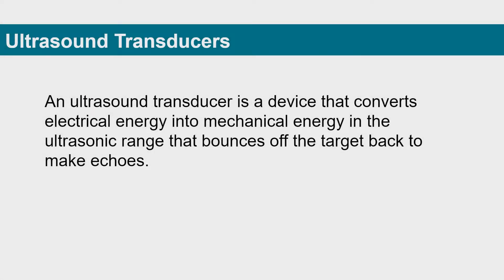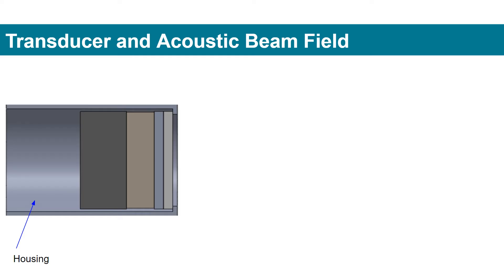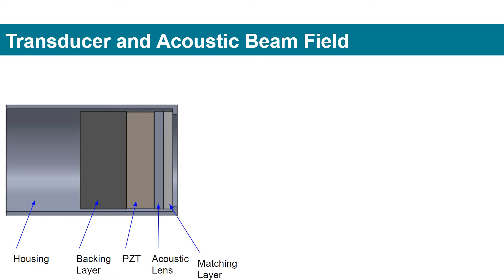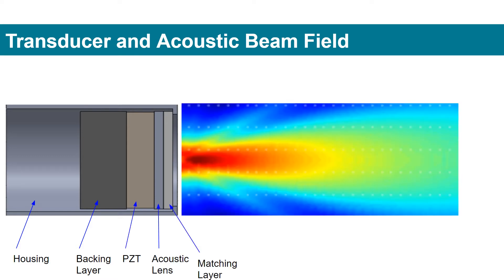An ultrasound transducer is a device that converts electrical energy into mechanical energy in the ultrasonic range, that bounces off the target back to make echoes. A transducer is composed of a case or housing, backing layer, piezoelectric crystal or PZT, acoustic lens, and matching layer. Its acoustic beam field looks like this.